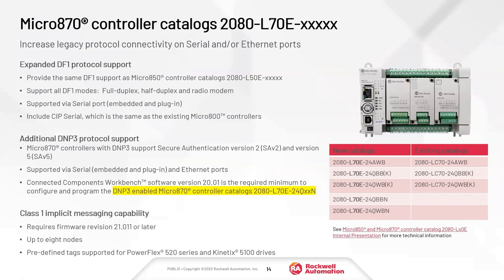The 870E follows the same story. The previous 2080-LC70 models will become discontinued in the near future and will be replaced by the L70E — direct replacements with enhanced communication capabilities. Same as the 850, they gain DF1 protocol support, and the key difference is DNP3 support. Importantly, if you need DNP3 you must purchase the N model — there's an N at the end of the catalog number indicating DNP3 capability.